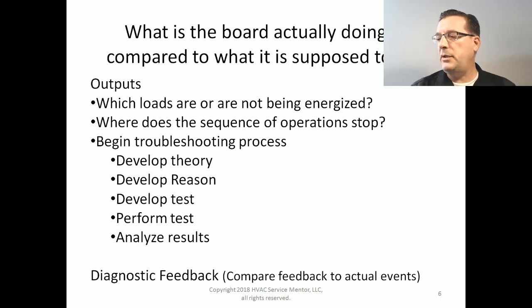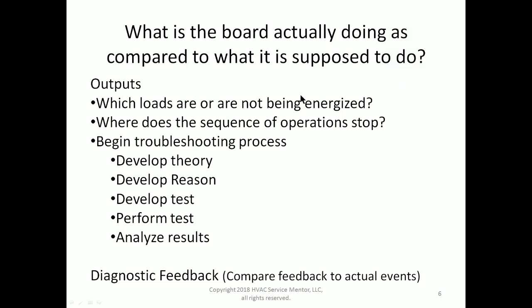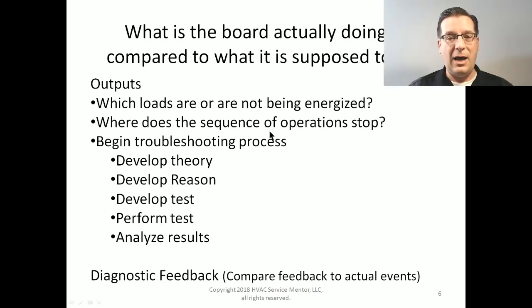The next thing that we're going to do is compare what the control board is actually doing to what it is supposed to do. Once we've identified that the board is in fact getting an input operational command, is it giving the correct outputs? So now we need to look and see what loads are or are not being energized. Where does the sequence of operations stop? This goes right along with our troubleshooting ideas. We identify where the sequence of operations stops, and that's where we begin our actual troubleshooting process.